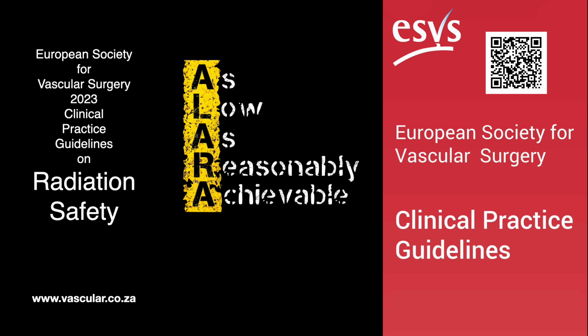And what is air kerma in simple terms? Think of it as the kinetic energy released from the x-rays into a small volume of air. It represents the radiation intensity at a point. Okay, intensity. And there's this concept of the patient entrance reference point. Yes, this is important. Imagine a point 15 centimeters away from the C-arm's isocenter, back towards the X-ray source, which is usually under the table in vascular suites. The cumulative air kerma at this reference point, sometimes called CAK in the U.S., gives you a good estimate of the radiation dose hitting the patient's skin surface right where the beam enters. Got it. So AK is like the dose rate hitting the skin entry point. What's the other main parameter?